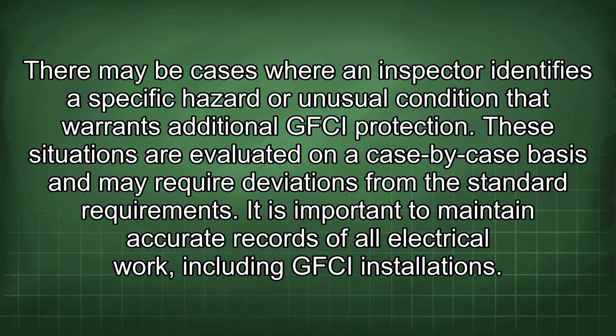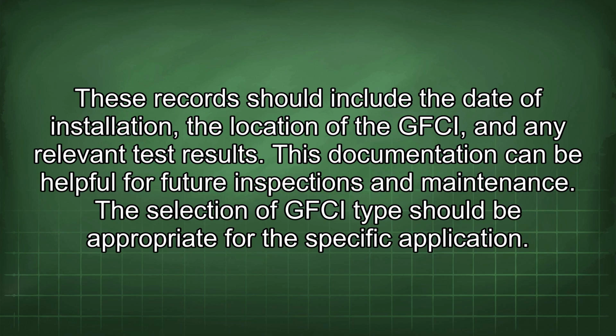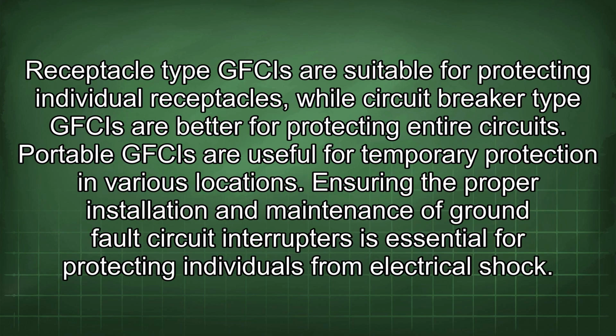It is important to maintain accurate records of all electrical work, including GFCI installations. These records should include the date of installation, the location of the GFCI, and any relevant test results. This documentation can be helpful for future inspections and maintenance. The selection of GFCI type should be appropriate for the specific application. Receptacle type GFCIs are suitable for protecting individual receptacles, while circuit breaker type GFCIs are better for protecting entire circuits. Portable GFCIs are useful for temporary protection in various locations.